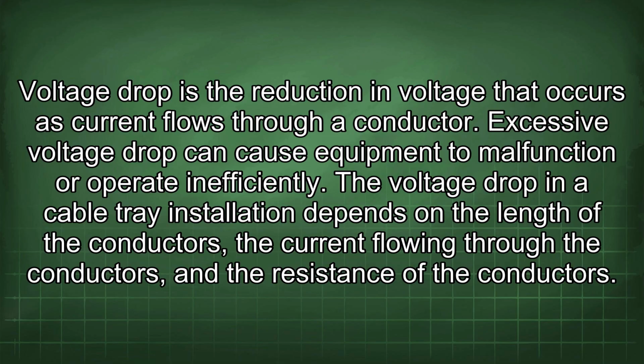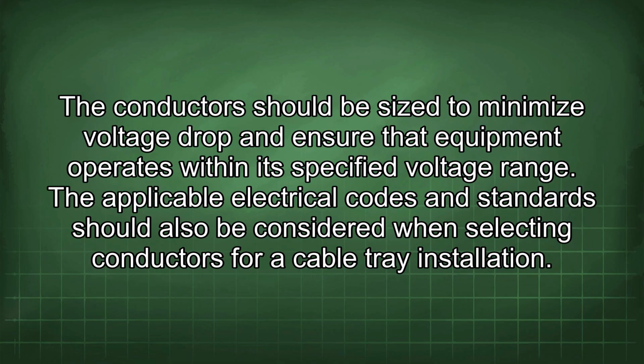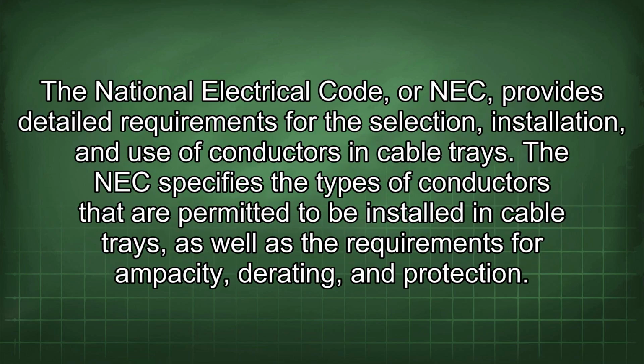The voltage drop in a cable tray installation depends on the length of the conductors, the current flowing through the conductors, and the resistance of the conductors. The conductors should be sized to minimize voltage drop and ensure that equipment operates within its specified voltage range. The applicable electrical codes and standards should also be considered when selecting conductors for a cable tray installation. The National Electrical Code, or NEC, provides detailed requirements for the selection, installation, and use of conductors in cable trays. The NEC specifies the types of conductors that are permitted to be installed in cable trays, as well as the requirements for ampacity, derating, and protection.